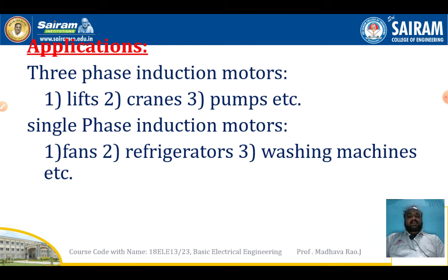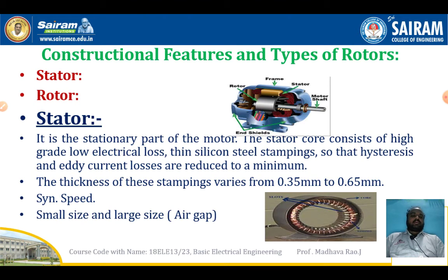three-phase induction motor. Next we will see the constructional features of three-phase induction motor. Basically these induction motors have mainly two parts, one is the stator and the other is the rotor. Stator is a stationary part, rotor is a rotating part, right? Stator is the stationary part of the motor, the stator core consisting of high grade, low electrical loss, thin silicon steel stamping so that hysteresis and eddy current losses are reduced to a minimum.